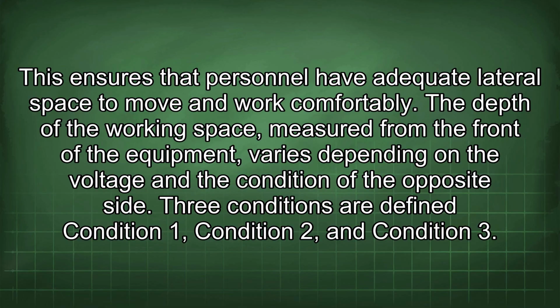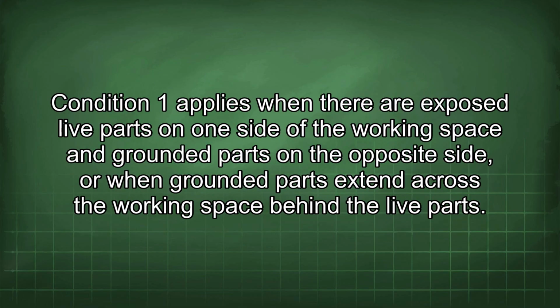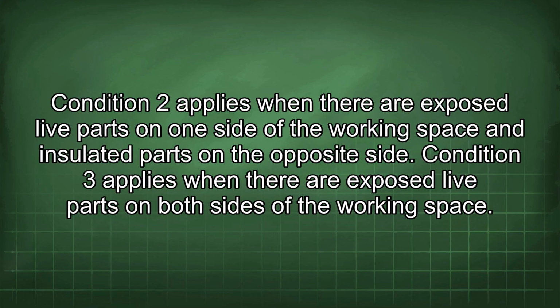The depth of the working space, measured from the front of the equipment, varies depending on the voltage and the condition of the opposite side. 3 conditions are defined: Condition 1, Condition 2, and Condition 3. Condition 1 applies when there are exposed live parts on one side of the working space and grounded parts on the opposite side, or when grounded parts extend across the working space behind the live parts. Condition 2 applies when there are exposed live parts on one side of the working space and insulated parts on the opposite side. Condition 3 applies when there are exposed live parts on both sides of the working space.